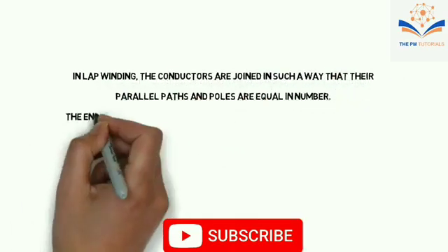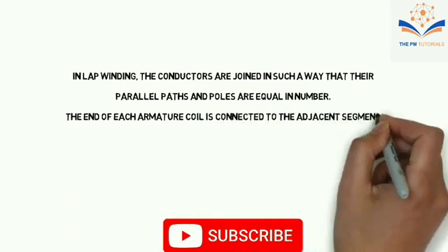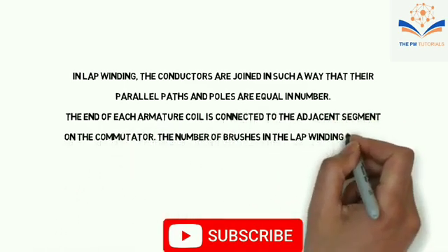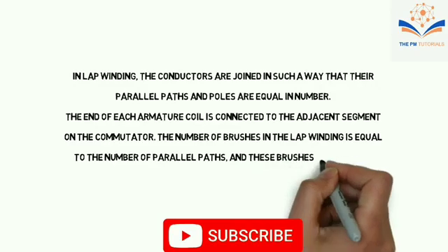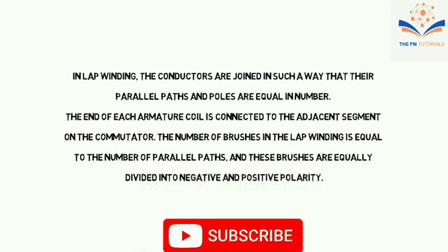In the construction of lap winding, the conductors are joined in such a way that the parallel paths and poles are equal in number. The end of the armature coil is connected to the adjacent segment on the commutator. The number of brushes in the lap winding is equal to the number of parallel paths. These brushes are equally divided into negative and positive polarity.